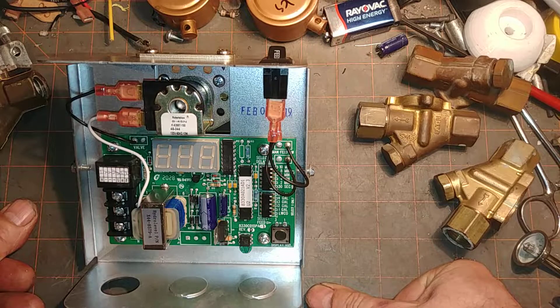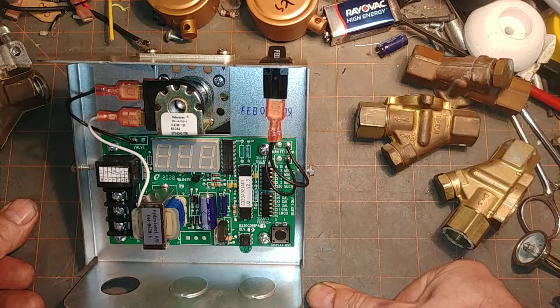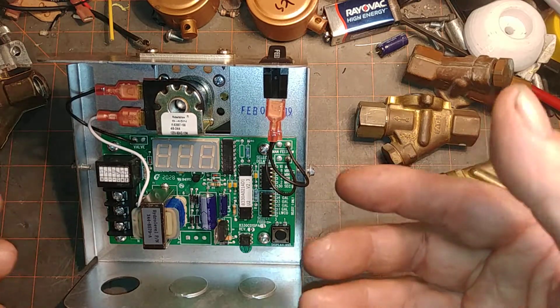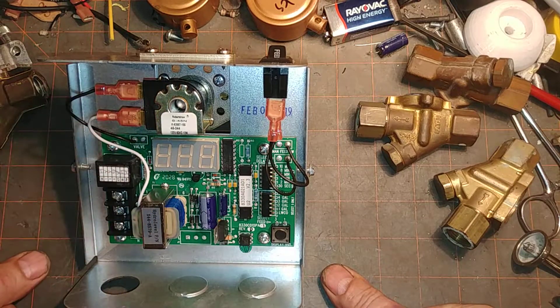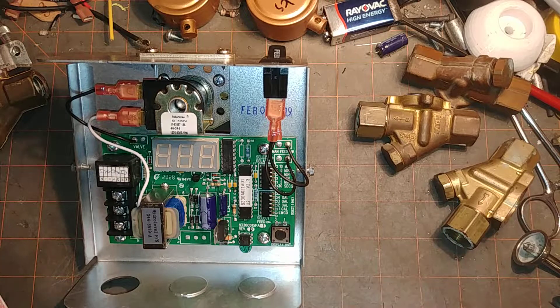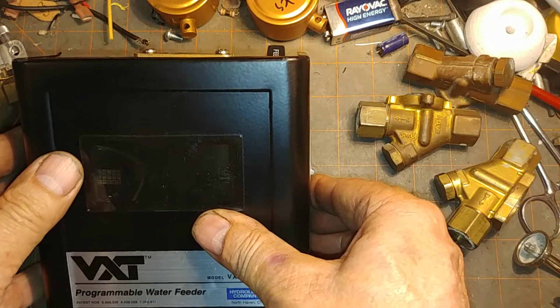In my experience, the electronics is pretty stable. Usually when the electronics fails, it's because something is wrong with the circuitry and it simply won't work at all — it will not send spurious information to the valve. I've seen one out of the scores and scores that I've encountered over the decades where the unit had failed and was sending improper information to the valve.